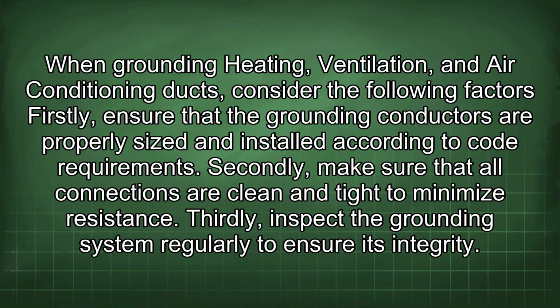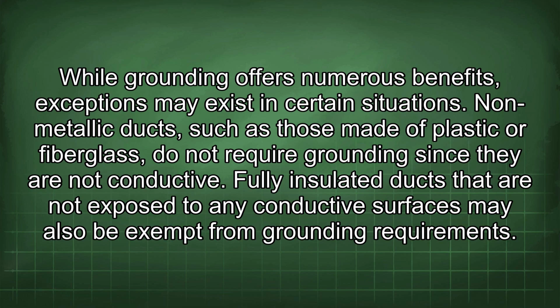When grounding heating, ventilation, and air conditioning ducts, consider the following factors. Firstly, ensure that the grounding conductors are properly sized and installed according to code requirements. Secondly, make sure that all connections are clean and tight to minimize resistance. Thirdly, inspect the grounding system regularly to ensure its integrity. While grounding offers numerous benefits, exceptions may exist in certain situations. Non-metallic ducts, such as those made of plastic or fiberglass, do not require grounding since they are not conductive. Fully insulated ducts that are not exposed to any conductive surfaces may also be exempt from grounding requirements.